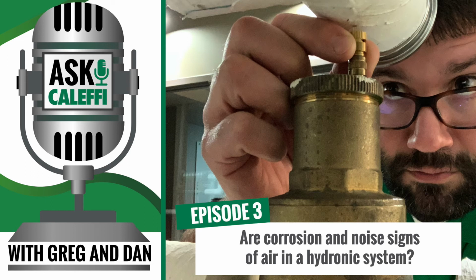Excellent. We touched on sizing a bit, but we could brush up on it a little more. Whenever sizing one of these, whether it's a dirt separator, air separator, hydraulic separator, or mixing valve, we always want to base that off of the GPM flow rate. And that's total GPM. You might have a multiple boiler application where you have a hydraulic separator and a header coming off of that, with two or three boilers tied into it.